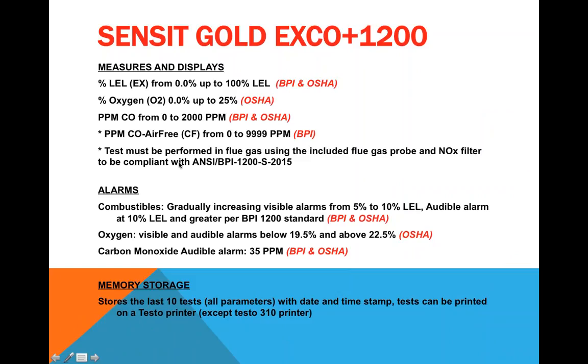So the specs on this product, it does measure and display the LEL, the oxygen. Again, these are all the things we talked about. ppm CO, it does ppm CO air free for BPI. It does have a proper probe that's required by the standard. It does the 10% LEL. The oxygen, it will give you visual and audible alarms when the oxygen drops in and out of the range, and a carbon monoxide alarm. It also stores tests so that they can be used for your BPI evaluations.